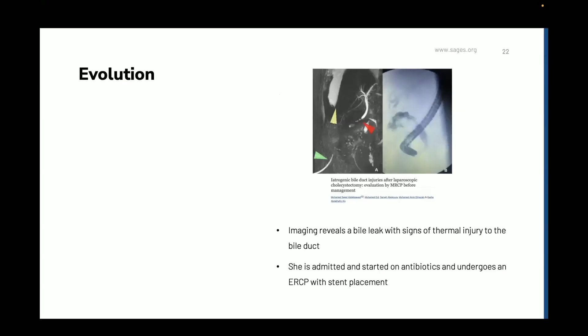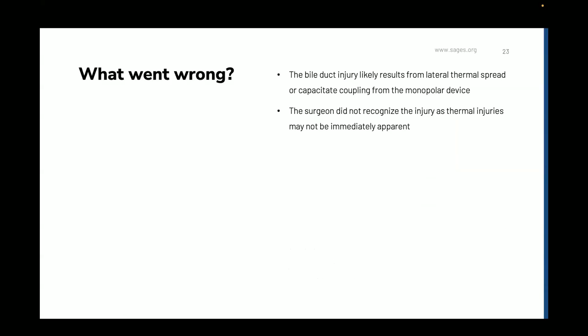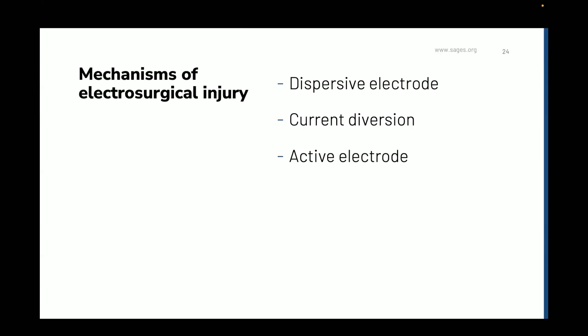So what went wrong in this case? The bile duct injury likely resulted from thermal spread or capacitive coupling from the monopolar device, and I'll talk about what these terms mean. The surgeon didn't recognize the injury, as thermal injuries may not be immediately apparent. Mechanisms of electrosurgical injury can be divided into 3 broad categories: from the dispersive electrode, current diversion, or the active electrode.